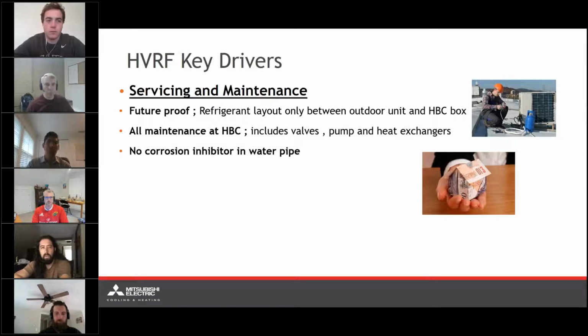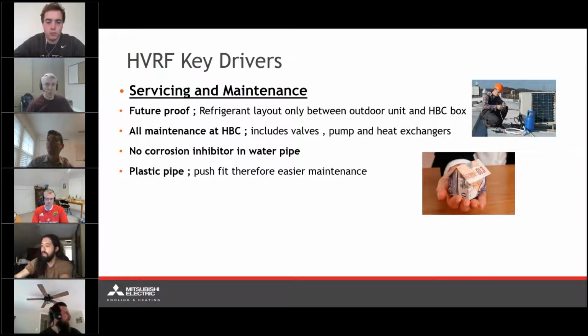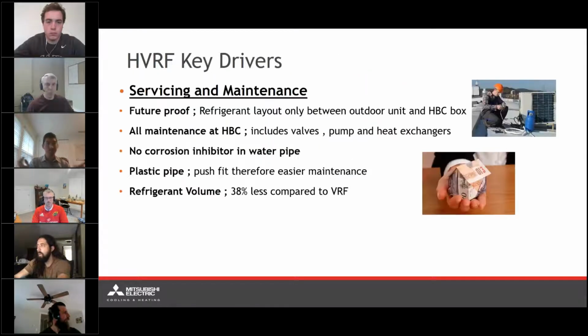Again, we're going to be wanting corrosion inhibitors in the pipes. We're not going to want to see the pipes just slowly degrade over time. Plastic piping, easy push fits. We're reducing refrigerant volumes up to 38%. So all that just from a service and maintenance standpoint, we're seeing a lot of improvements.